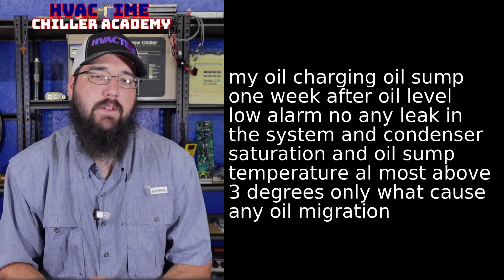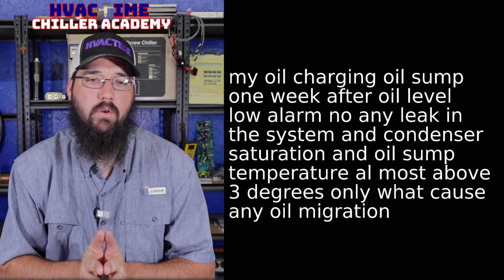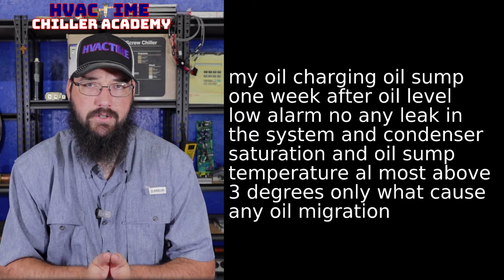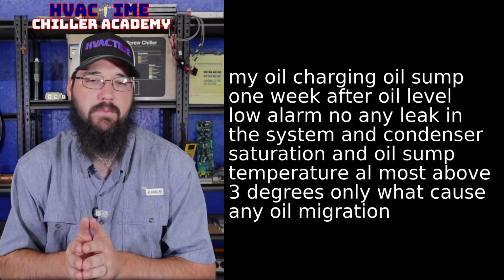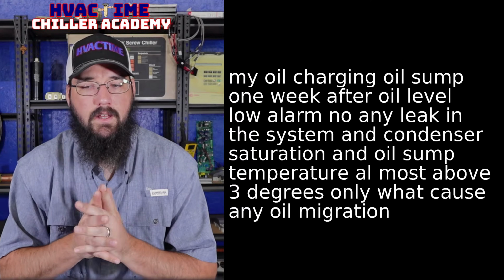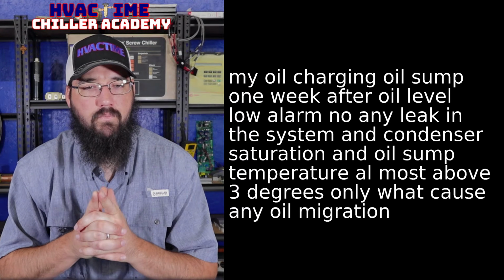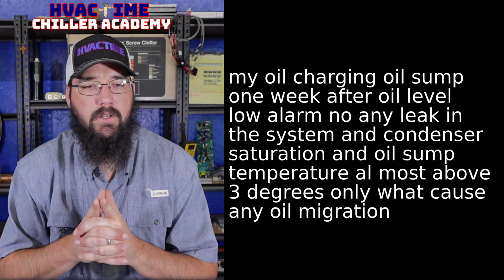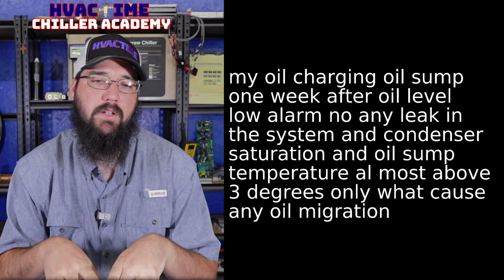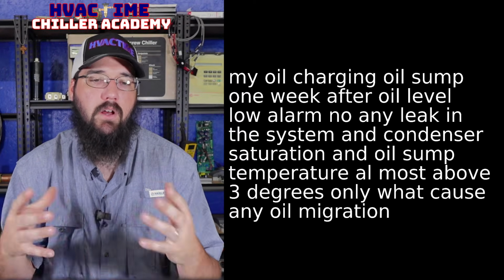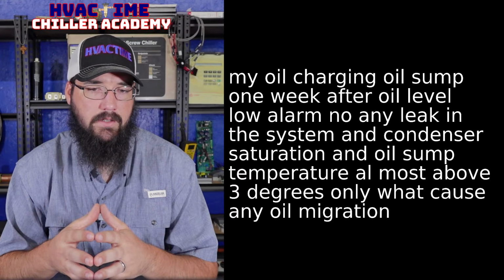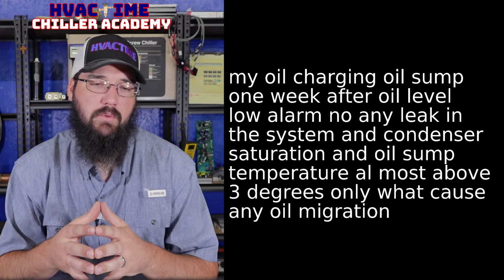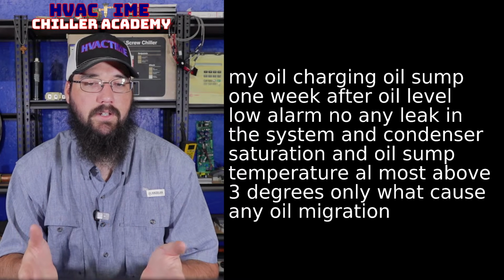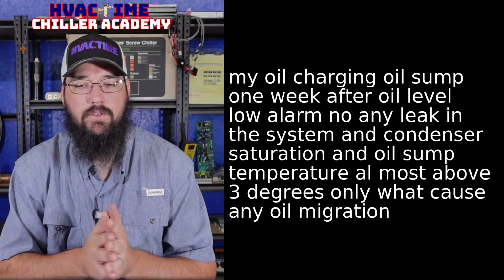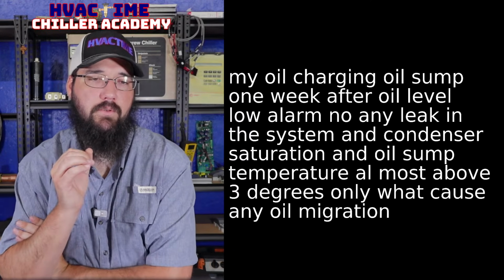So, okay, it ran for a week. We have a low oil level alarm. So we're thinking migration since we don't have a big oil slick underneath the machine. No leak in condenser system, condenser saturation, and oil. So we're keeping condenser sat and oil sump temp up, if I'm tracking. I just want to make sure the oil heater is actually functioning. How do I approach this question?